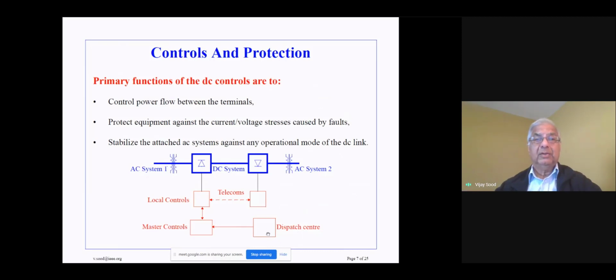And the controls are broken down into master controls and local controls. So we have a dispatch center where a power order could be sent over to the master controller. The master controller will just convert these into local variables like DC current or DC power, and then send that to the local controls. The two local controls for the rectifier and inverter may or may not be connected by telecommunications. If you want fast behavior of the system, then you'll need to have some kind of telecommunication link. The telecommunication link is not necessary, but you can still operate the DC system without telecommunication, but it has to be a very slow operation in that case.